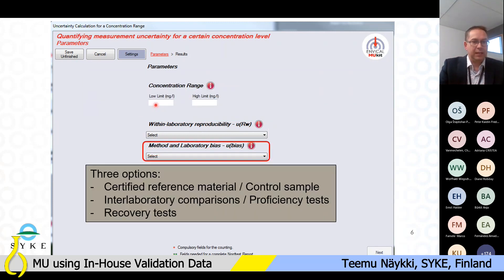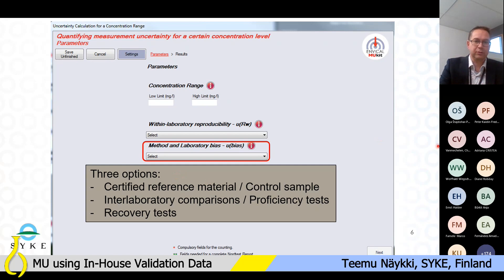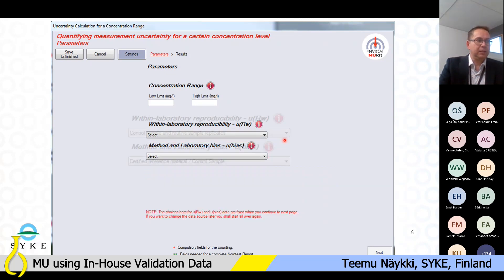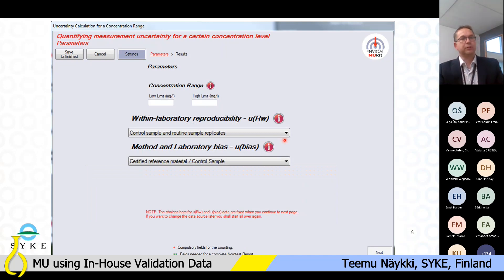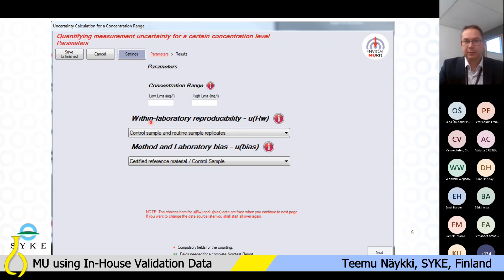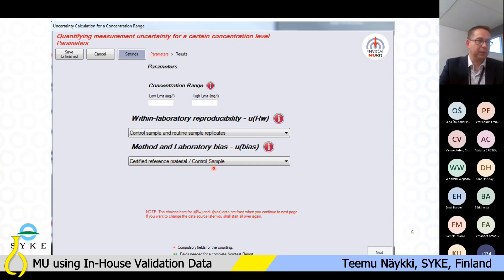For method and laboratory bias, there are three options: you use the results of certified reference material, a control sample, or you use inter-laboratory comparisons, proficiency tests, or data from recovery tests. In this example, I chose to use the control sample and routine sample replicates — the real wastewater samples — for within-laboratory reproducibility, and the results from CRMs for method and laboratory bias.